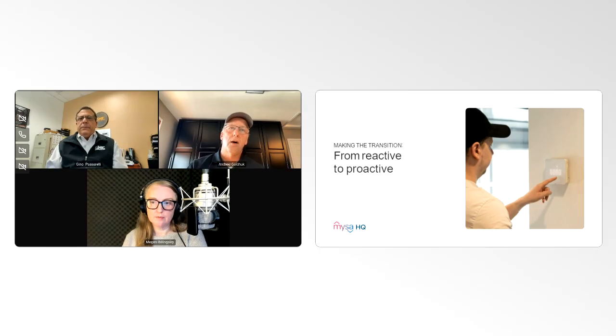You can also see how the HVAC system recovers from setbacks. This is where businesses are going to save energy during the setback or unoccupied periods, but how quickly does that HVAC system recover from a setback period? A lot of that shows the performance of the HVAC system itself. When we look at runtime reports, it helps compare baseline operation against other units and understand the performance of the HVAC system. You can detect abnormalities or changes over time, indicating potentially a failing part, a dirty evaporator coil, or a plugged filter.